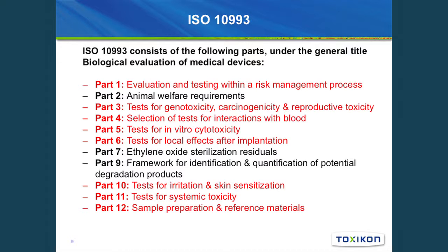Okay, these are going to be how to determine what biocompatibility testing is required, how to conduct some of those biocompatibility tests, and either the in vitro or in vivo aspects. The 10993 series does go into 20 total parts. Parts 13 through 20 are predominantly focused on material characterization, the chemistry, degradation, and how to assess that data, which will be presented on another talk.